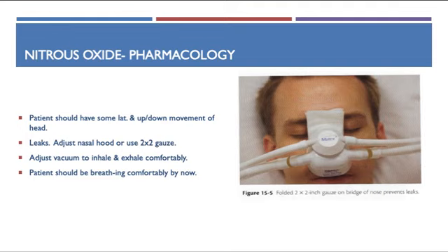If you happen to find that there are some leaks between the nasal hood and the patient's skin, then you can use a 2x2 gauze to help block some of those leaks. You do want to put it like it shows in the picture, flat and not rolled up. So don't roll up the gauze and stick it into any gaps, because it will probably move on you and it'll start leaking again.